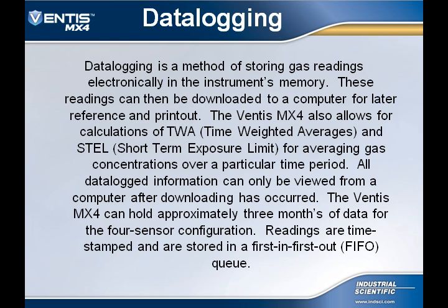Data logging is a method of storing gas readings electronically in the instrument's memory. These readings can be downloaded to a computer for later reference and printout. The Ventis MX4 also allows for calculations of TWA, time-weighted averages, and STEL, short-term exposure limit, for averaging gas concentrations over a particular time period. All data logging information can be viewed from a computer after downloading has occurred.